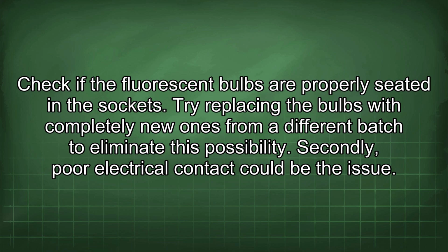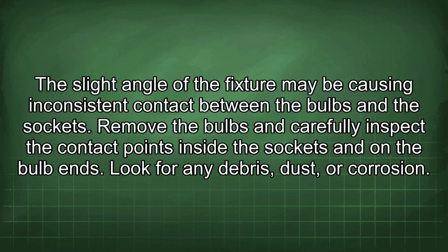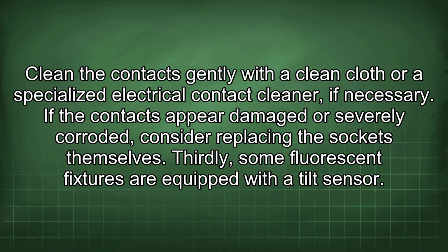Secondly, poor electrical contact could be the issue. The slight angle of the fixture may be causing inconsistent contact between the bulbs and the sockets. Remove the bulbs and carefully inspect the contact points inside the sockets and on the bulb ends. Look for any debris, dust, or corrosion. Clean the contacts gently with a clean cloth or a specialized electrical contact cleaner, if necessary. If the contacts appear damaged or severely corroded, consider replacing the sockets themselves.